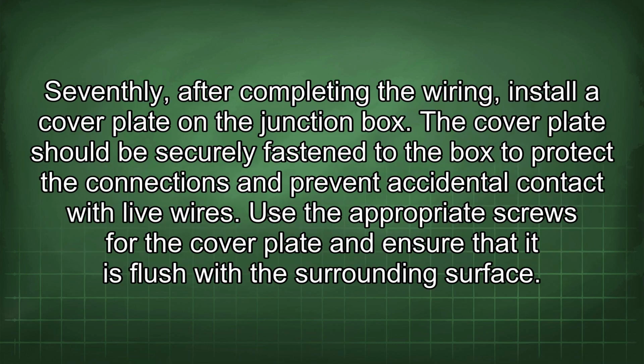Seventhly, after completing the wiring, install a cover plate on the junction box. The cover plate should be securely fastened to the box to protect the connections and prevent accidental contact with live wires. Use the appropriate screws for the cover plate and ensure that it is flush with the surrounding surface.